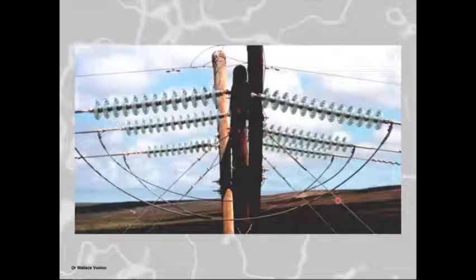So we went up and investigated things a little bit further. Obviously there are birds now, so we know there are birds, but they still don't want to accept it. So then what they did find on the inspection is that the center phase jumper is pulled in more than the outer phase jumpers, and there's less clearance between the center phase and Earth, okay? There's less clearance between center phase and Earth.